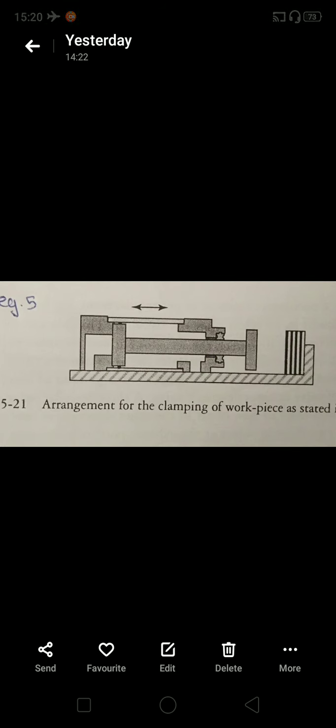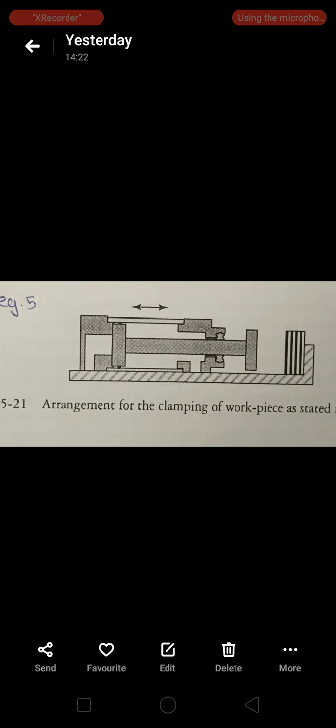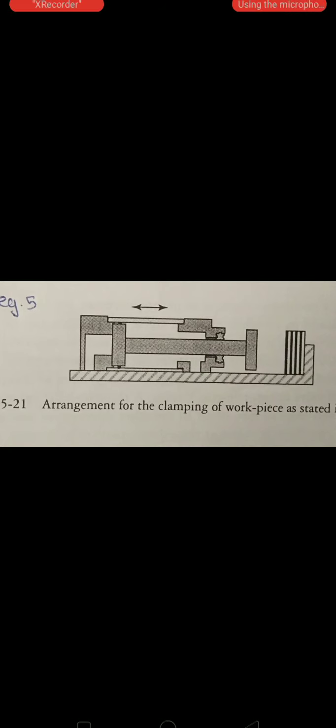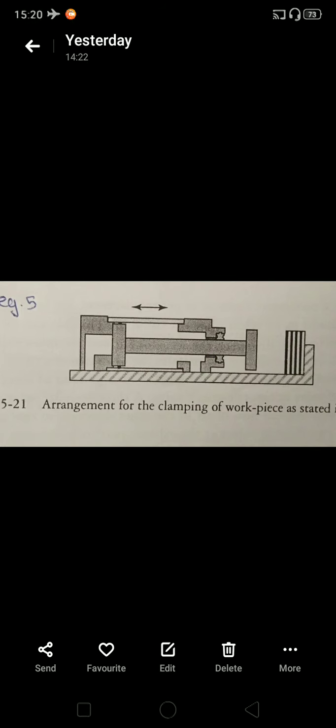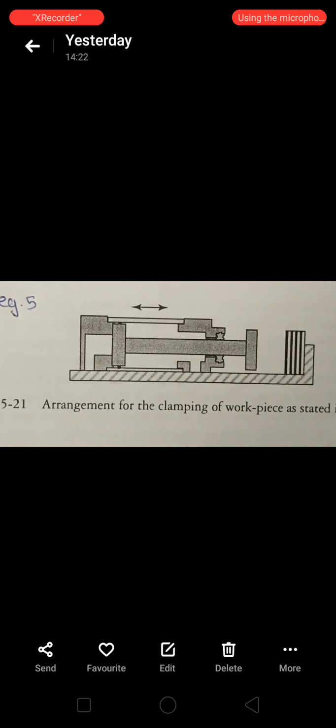Compressed air is actually a fast working medium for both linear and rotary motion. The operating speed of a normal cylinder ranges up to, let's say, 1.5 meters per second. The operating speed of a pneumatic actuator is determined by how quickly it can be filled with air from one side through one port and exhausted at the other side through the other port. The maximum natural speed of a double acting cylinder is governed by a number of factors, which you will learn in theory also.